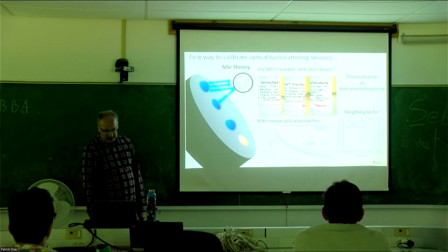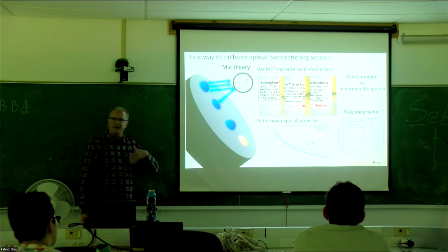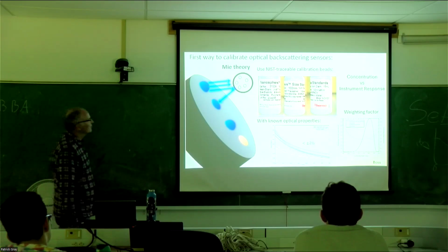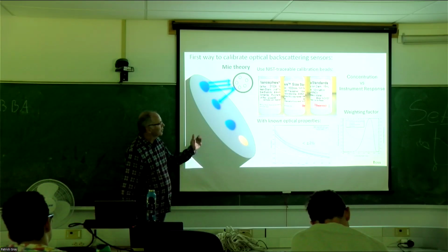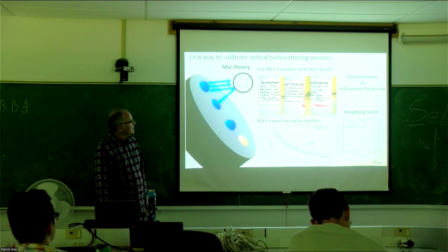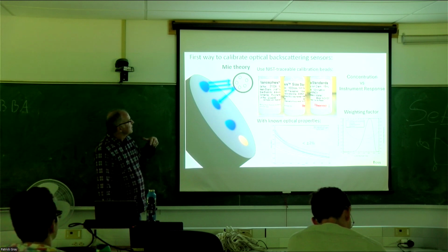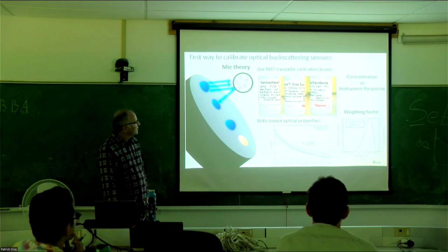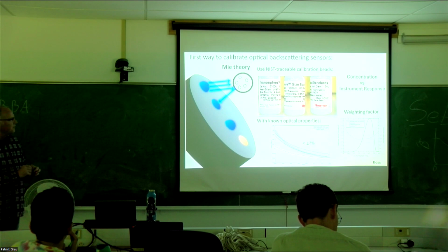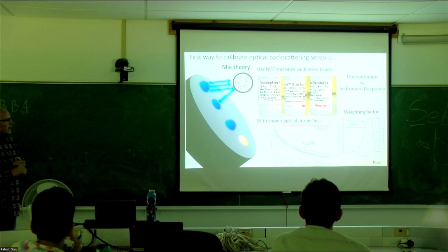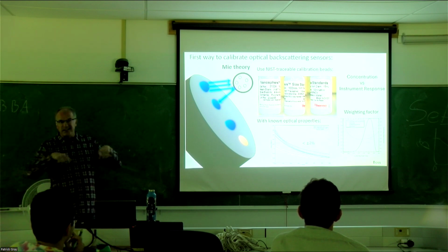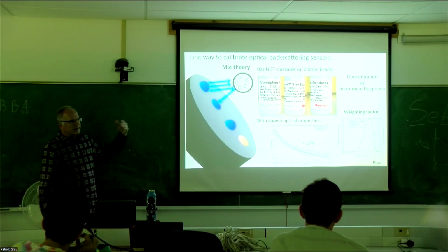So for an optical backscatter measurement, I think we've talked about it. It was great that this came after Patrick's talk. The reference standard typically, and most often, or actually for almost all of them, is the nanosphere, the spheres and nanosphere. So what we have here is a sphere that's of very high quality. You can buy these reference standards. You know what the actual diameter is, the particle size distribution around that diameter. It's very, very low. These are all NIST traceable.